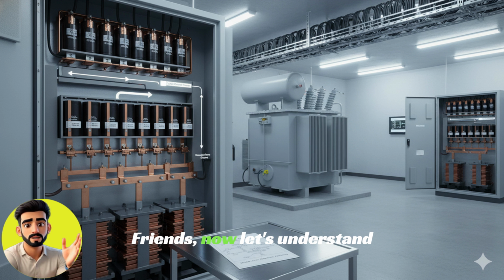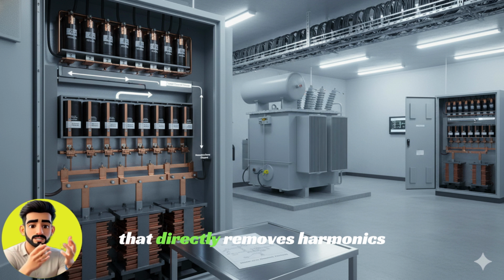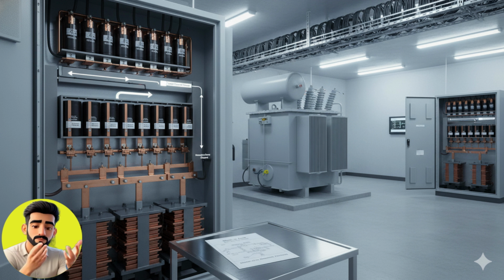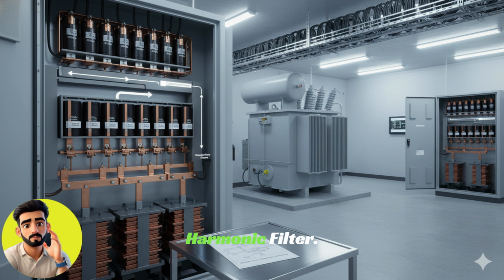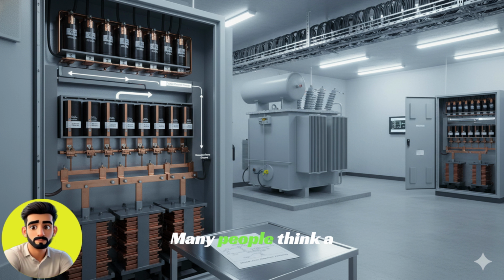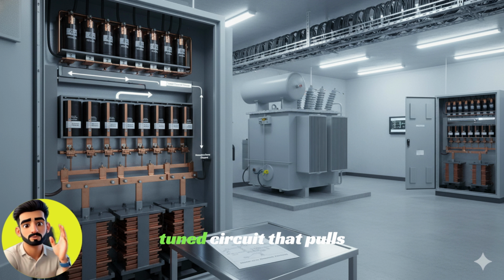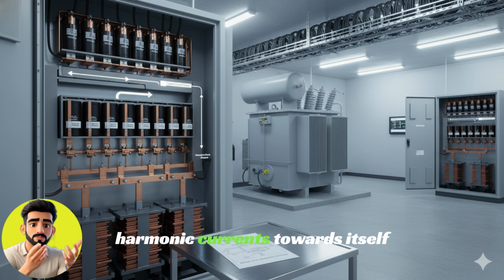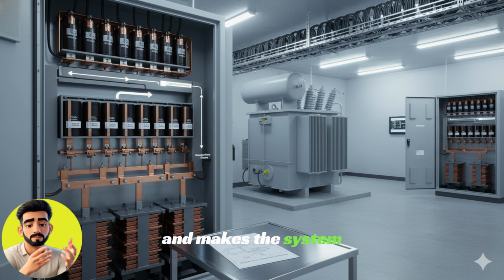Friends, now let's understand a very powerful solution that directly removes harmonics from the system. Its name is passive harmonic filter. Many people think a filter is just a capacitor and reactor, but in reality, a passive filter is a carefully tuned circuit that pulls harmonic currents towards itself and makes the system clean. Let's understand step by step how a passive harmonic filter works.